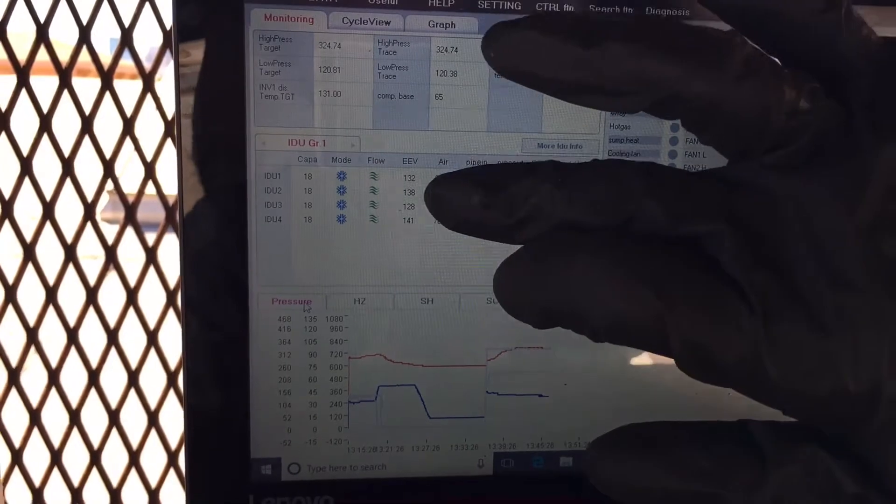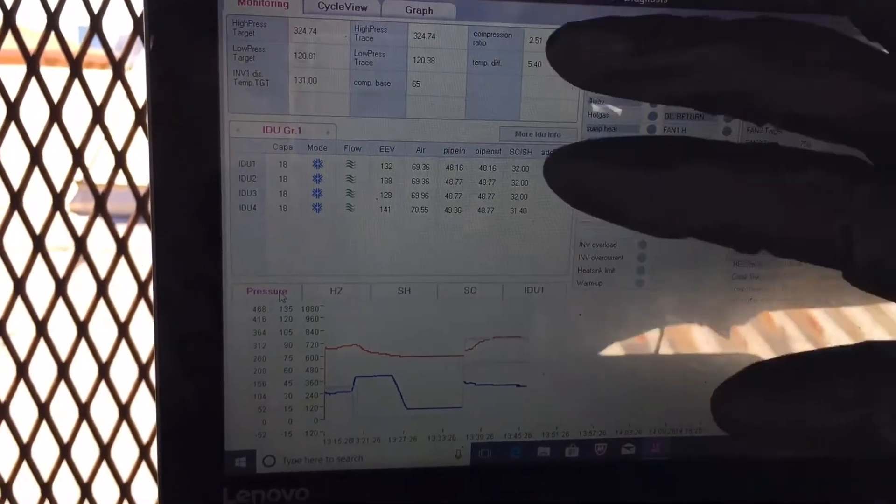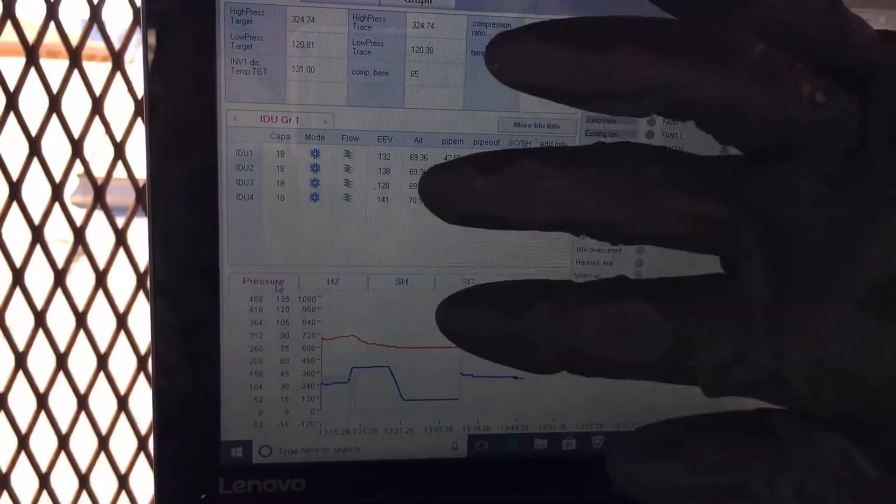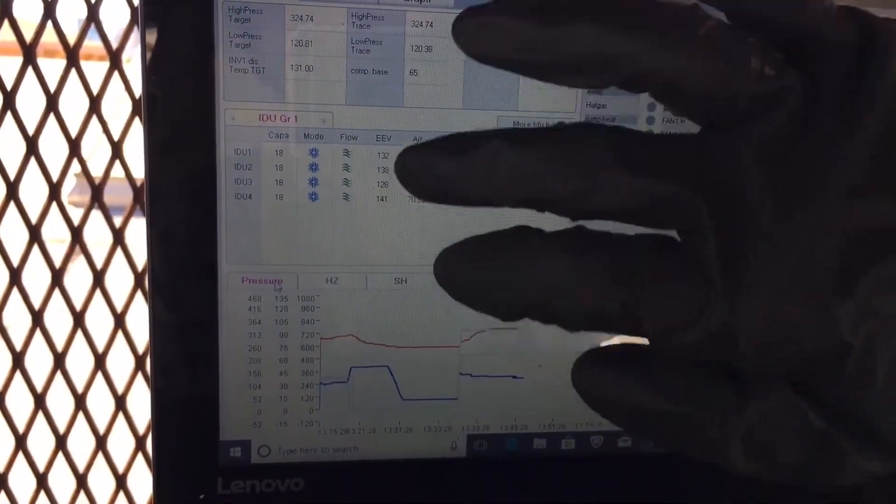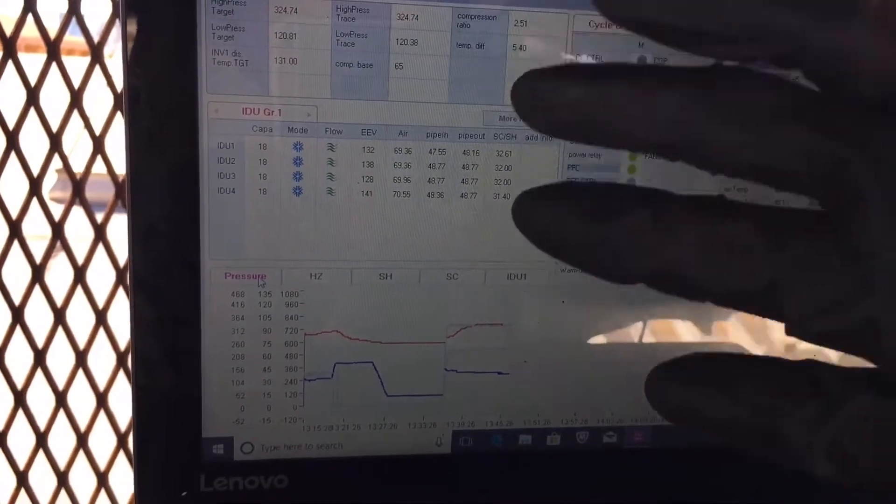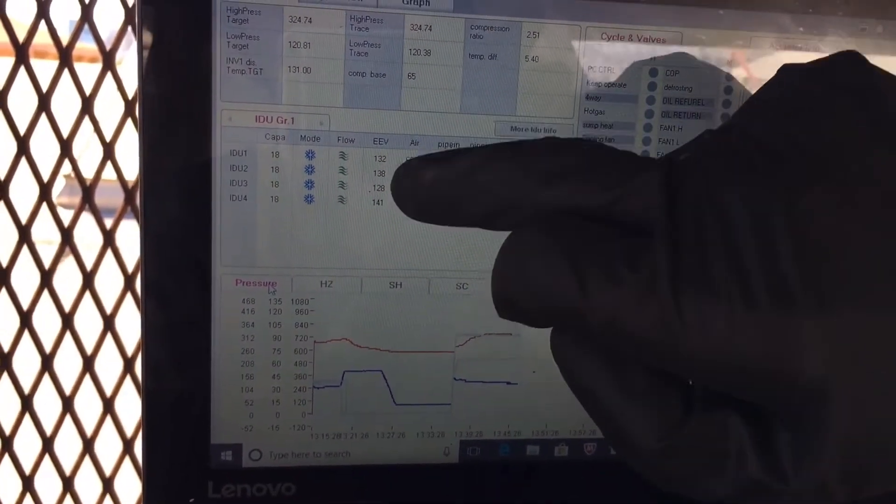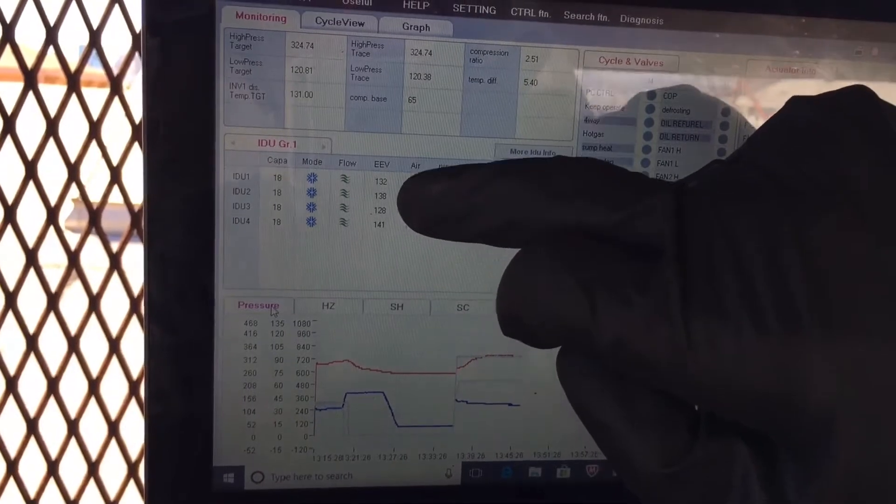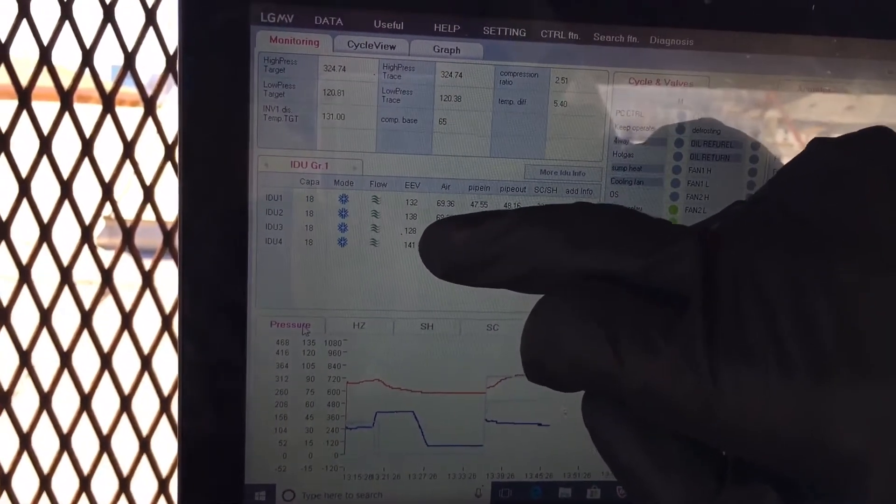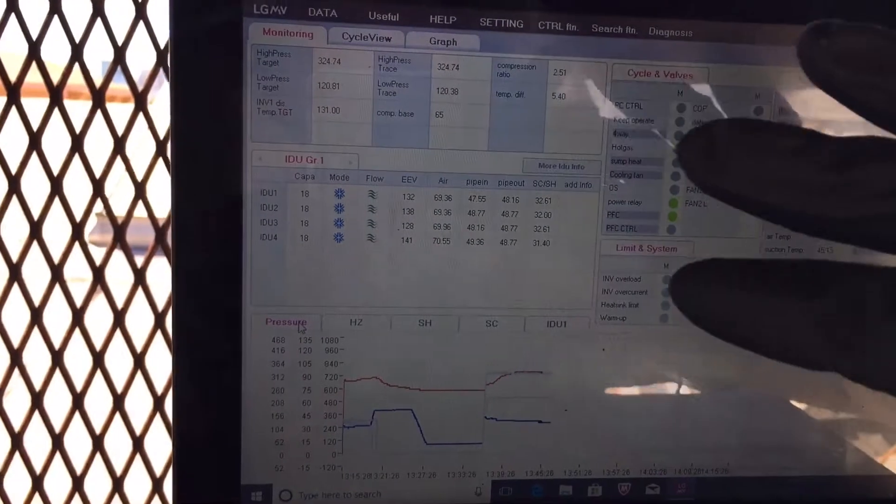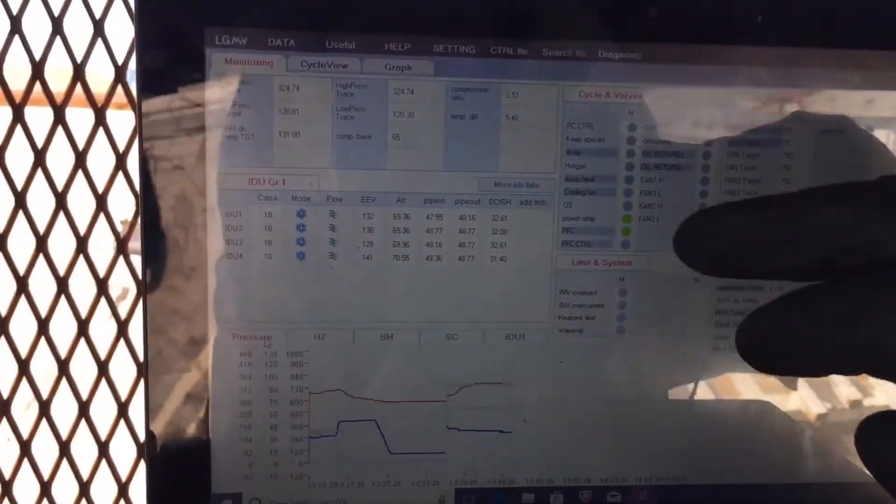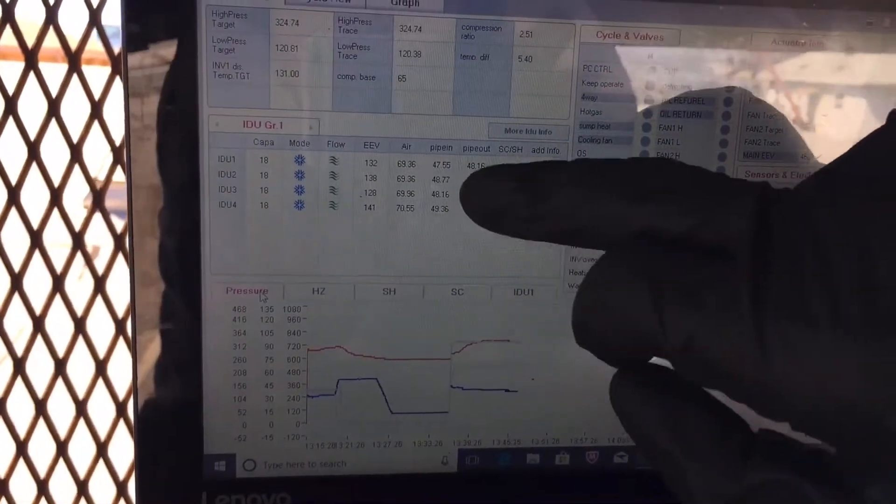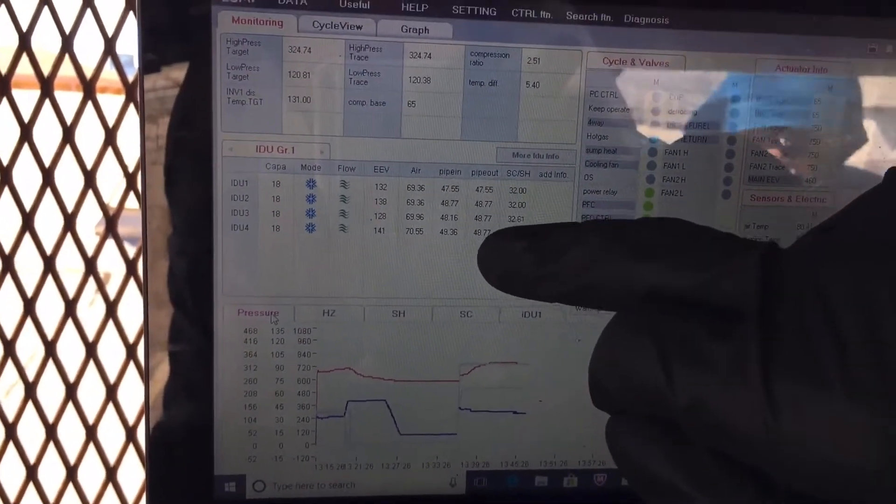Remember before our electronic expansion valves, there were that 450 or were they 600 on this unit? I can't, I've done so many of these in the last couple days that I can't, between 600 and 400 when they're really low. Look at our EEVs right now. We're at 132, 138, 128, 141 because we have enough refrigerant flow.